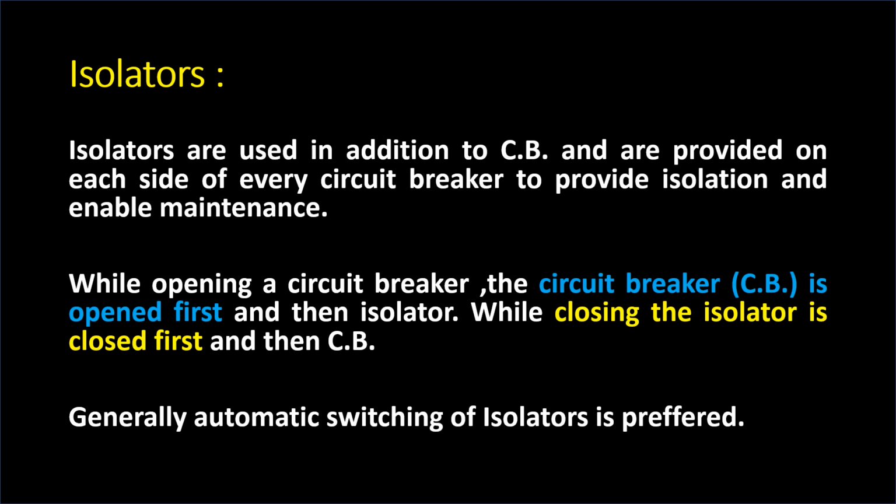While opening, the circuit breaker is first opened and then isolator. And if you want to close the system, then while closing, the isolator is closed first and then circuit breaker. And the reason behind it is that isolator never operates on load condition.